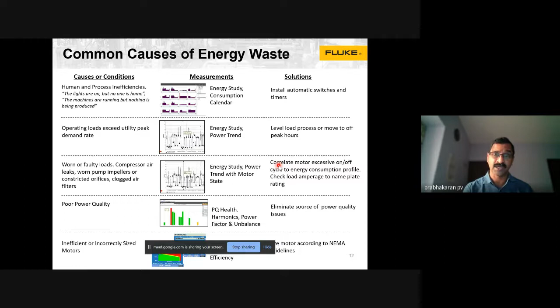I'm expanding on power quality and how it wastes energy consumption in your facility. With a sinusoidal waveform running in your facility, you have the power triangle, a two-dimensional diagram with kVAR, kVA, and kilowatt in the system, along with DPF, the displacement power factor.